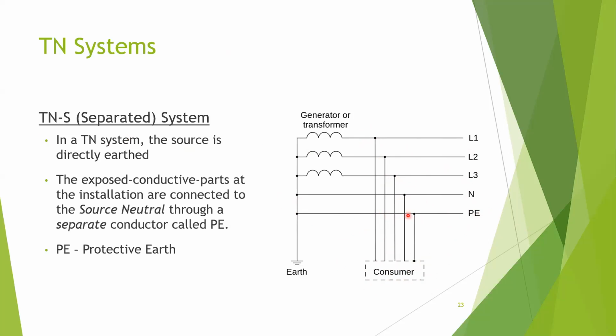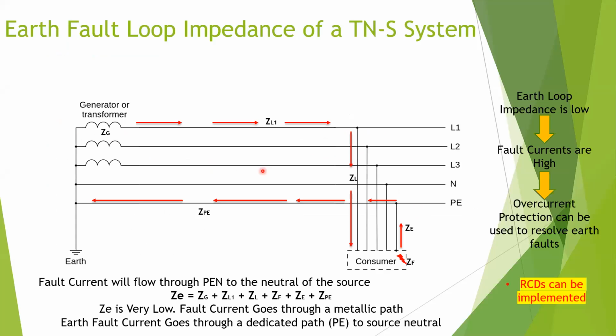That is everything you need to know about the TNS system, because we will do the earth loop impedance calculation for this. The loop characteristics are similar to TT, but the path is metallic. Okay, we will go to that. Earlier you may remember this is the loop impedance path for TNS. Earlier in TT we had this path through ground. There was a separate path to flow fault current, through ground or through soil. But here we are replacing that with a metallic conductor. I think you are following me. This is similar to TT, but the return is fully metallic.